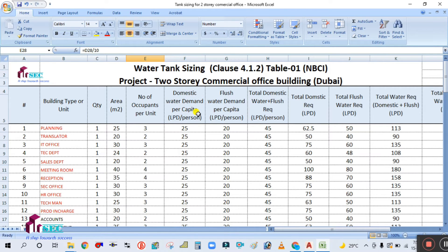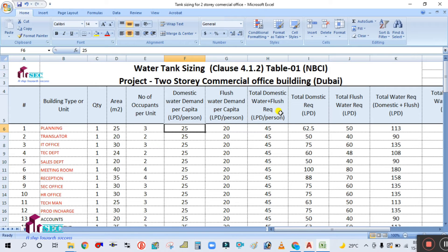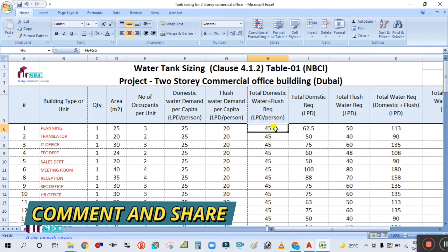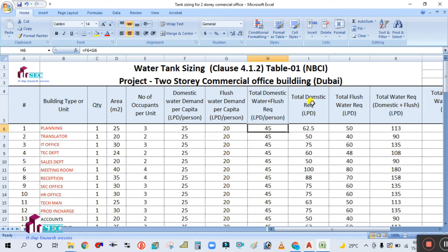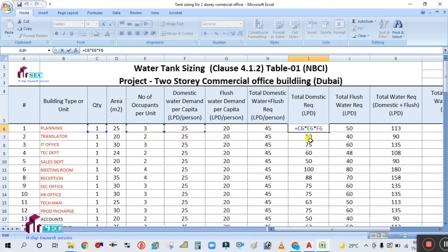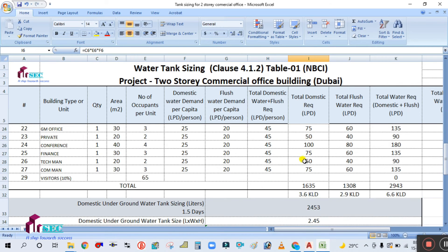The domestic water demand per capita is 25 liters per day per person for an office building, taken from NBC or DEWA standard. The flush water demand is 20 liters per day per person. Total is domestic plus flush water. Total domestic water required is calculated by multiplying the domestic water per day per person by the number of people and the quantity of offices.